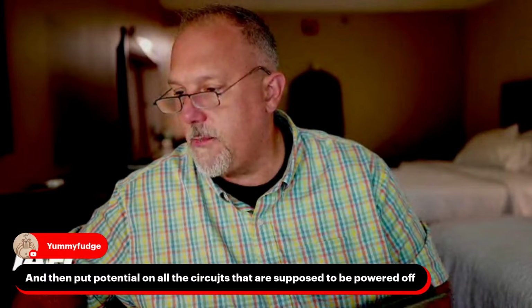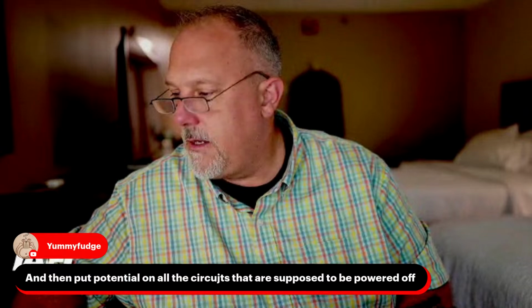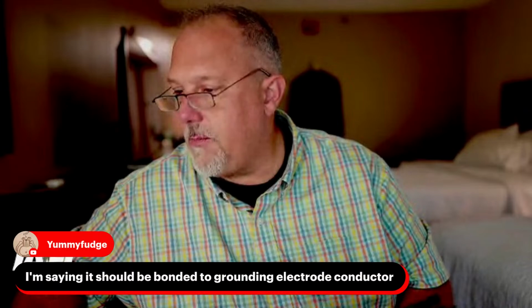Well, if it's not a separately derived system, you're still good because you would be interconnected with the service equipment where the bonding is done. That neutral, okay. So, I'm not sure if I can draw this or not. And that is for, it goes back to the source, right? David Engelhardt says it goes back to the source and then put potential on all the circuits that are supposed to be powered off. He's saying it should be grounded and bonded to the electrode conductor, but it is.